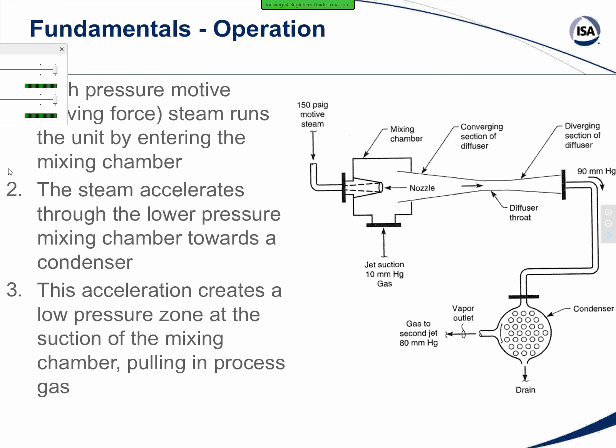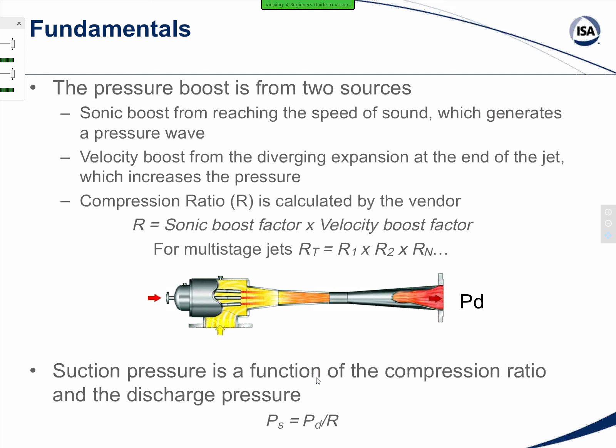The way a steam jet ejector works is by creating a low pressure area inside the jet that suctions gas from the targeted vessel. First, you inject high pressure steam, which is also called motive steam in most applications, into an entry mixing chamber shown here. The steam is going to accelerate through the converging and then diverging throat of the jet towards the condenser. The acceleration of gas creates a low pressure zone, very similar to how a low pressure zone is developed by air running over the top of an aircraft wing, which is what's actually creating the lift on that wing. The force from this low pressure zone can be very significant, allowing you to reach some pretty high vacuum levels, or low pressure levels.